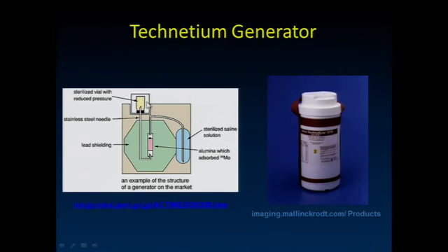And if you popped an evacuated vial onto the little needle, if you will, on the top of this, it would suck that fluid past that column, taking off the soluble technetium, and you'd end up with technetium in your vial, and hopefully it was working well, and you ended up with very minimal amount of breakthrough of molybdenum in your vial there. How many people still get a technetium generator like this delivered to their hospital here?